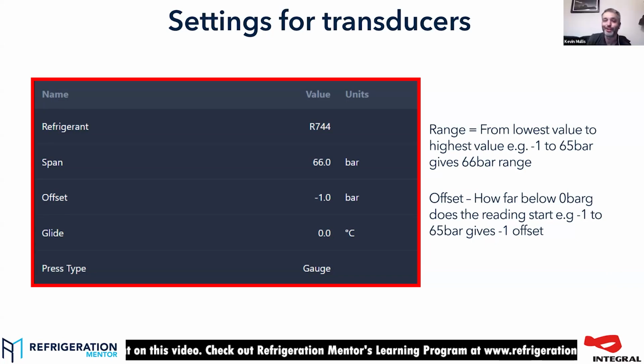It's trying to cover 66 bar, and you're asking it to be accurate at the very bottom of its range by 0.1 or 0.2. And that's important when you're doing those gases. CO2, if it moves by half a bar, it's like maybe half a degree. It's a lot less of a flap than it is if you move by half a bar on HFC.